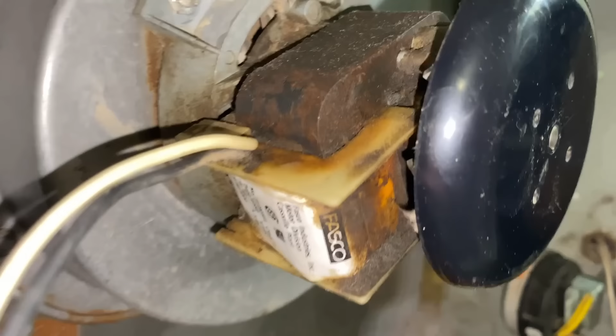But this runs, and when this runs, the pressure switch senses the pressure that is generated by the inducer assembly, and the pressure switch, which is an electric switch, will close once it knows this is running. So let's say, for example, this was not running. The machine doesn't know, right? But the machine knows that there's not any pressure at the pressure switch, and it will prevent the furnace from running. This is a gas valve. We have 2 wires going into it, which is 24 volts. So once all the safety circuit is good, the gas valve will energize and the gas will flow to the burners. And then as long as we have a means of ignition, that will ignite the gas.